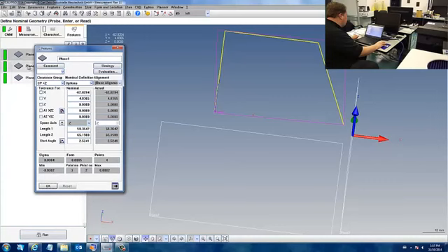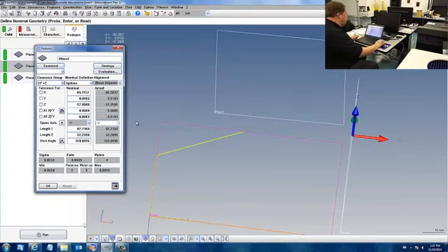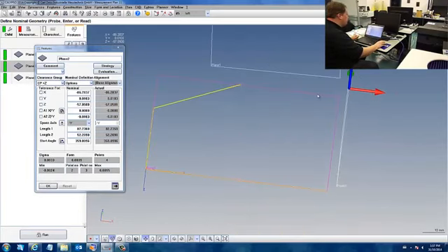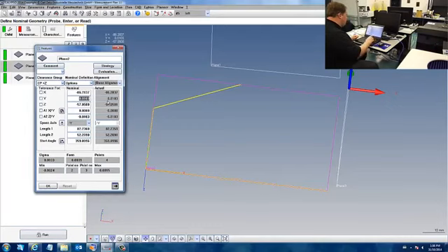If I take a look at plane number 2, there are some things that are definitely of concern. This face is meant to be the Y0, the Y origin. But as you see here, the value is actually just a little over 10 microns. Naturally, this is supposed to be 0. So let's edit that. But why wasn't it 0? Why did it have a value that was incorrect? That's because this face is not perfectly square to plane number 1. So this was the average value of our plane rather than the desired value.